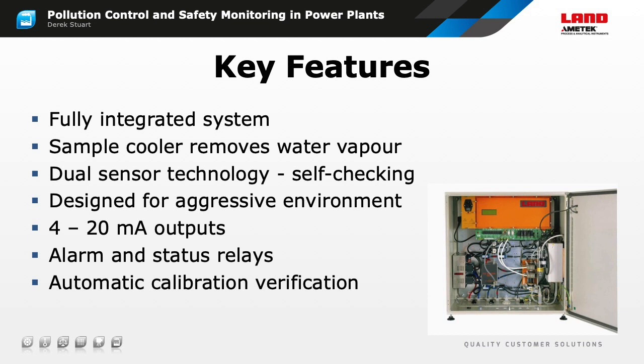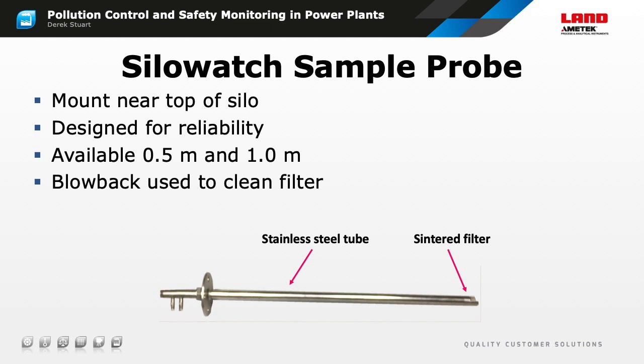It's important to verify correct operation of the sensor, otherwise a negative indication can give a false sense of security. For example, a sensor can be plugged with coal dust so that it no longer is exposed to the silo atmosphere, or the sensor can fail to zero output. That means a faulty instrument will indicate a CO concentration of 0, giving a false sense of security. The silo sample probe is a simple stainless steel tube with a sintered filter to prevent dust particles from entering the sample system and causing a blockage.